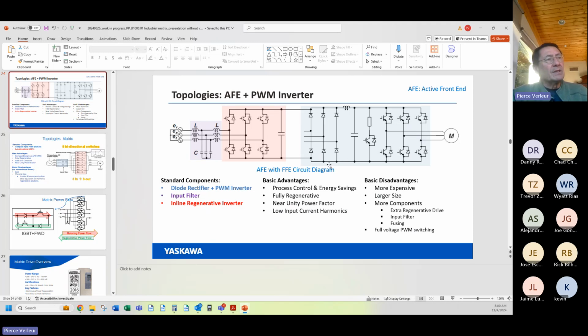And from an active front-end standpoint, they have to do that. We have to do that in our active front-end drive. Because if I don't have a higher effective voltage here than the line, current will only pass from the left to the right. And then I cannot use the transistors to shape the waveform that I'm drawing from the line, and therefore reduce the harmonic distortion, and therefore maintain the power factor. This design, active front end, you have to boost the voltage on the DC bus for the reasons of input section power factor performance. ABB says, oh, no, we're doing that also so that we can boost the voltage to the motor.